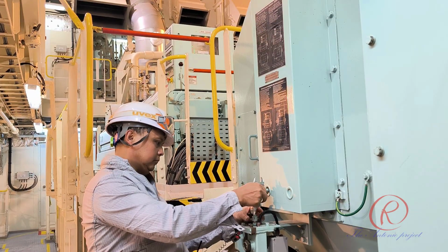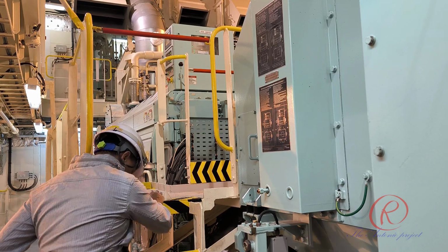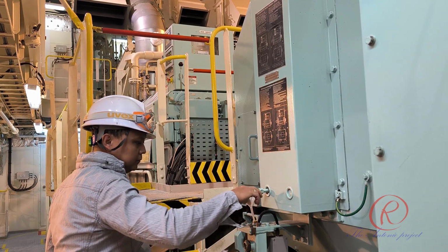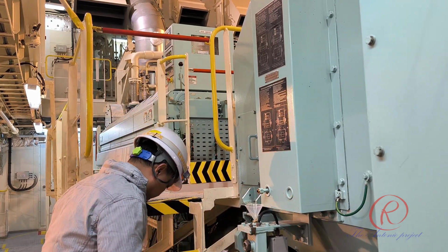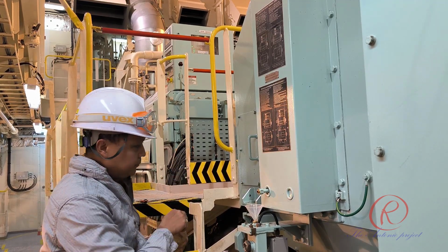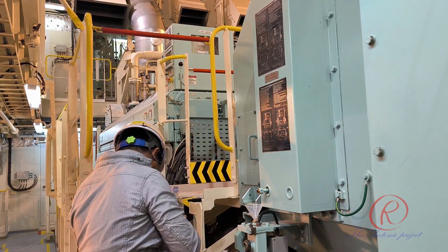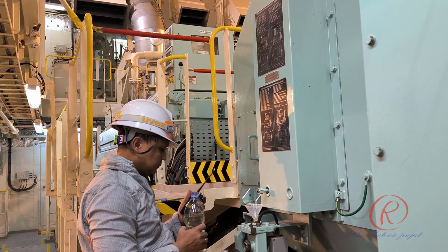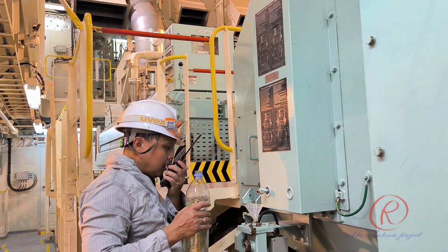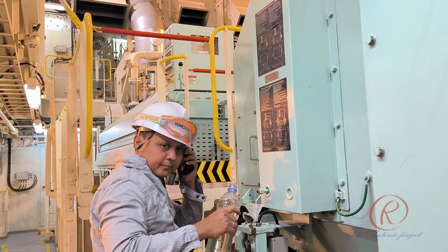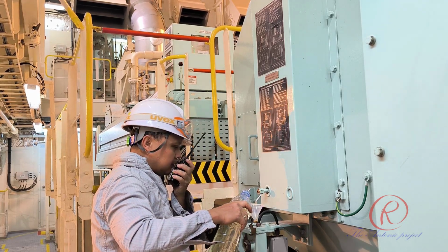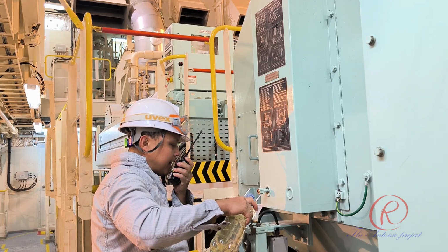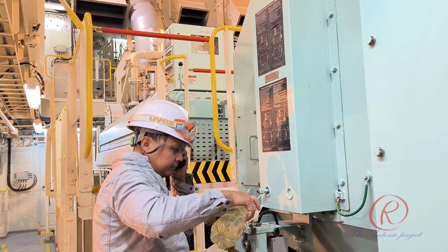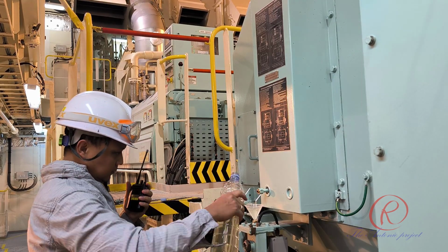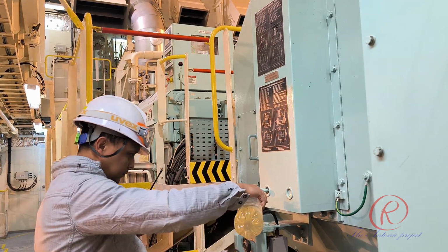Testing of air cooler water leakage. The purpose of this test is to confirm whether the water leakage sensor is in good working condition or not. The tools required for this test are as follows: spanners, a bottle of water, and a funnel. After the tube connector is disconnected, pour the water using the funnel into the leakage detector box. Check the water level on the sight glass of the box and confirm that the water is increasing.